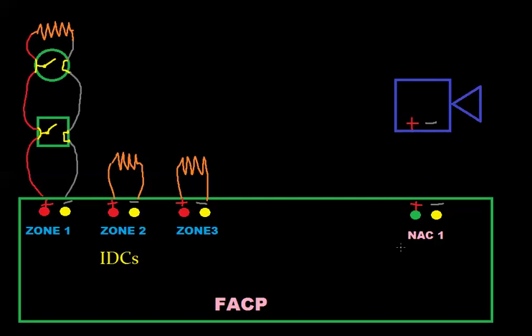We have a good idea now about how initiating device circuits work. How do the notification appliance circuits work? That's what these outputs are called. NAC1 stands for Notification Appliance Circuit. If we just put 24 volts connected positive to positive and negative to negative, just like on the initiating device circuits, we're going to have 24 volts sitting at this horn, which is going to turn it on. When that device has 24 volts, it is activated. But the circuit still has to be supervised. You can't just have zero volts because then you'd never know if somebody cut a wire. So the NAC still needs to see an end-line resistor.